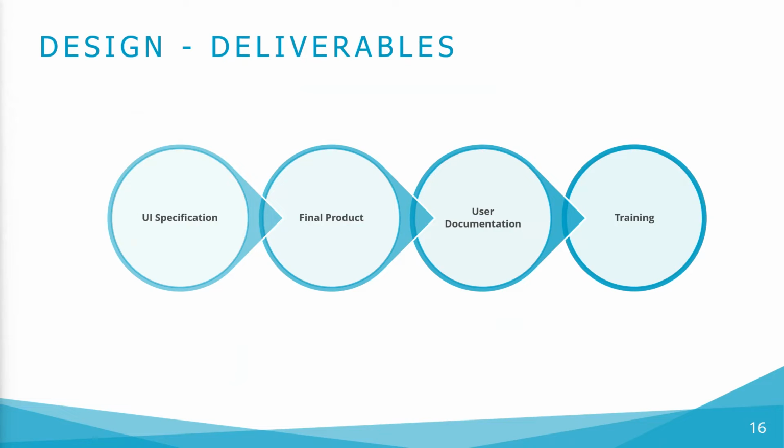After successful completion of the design step, update the following in the HFE report: description of intended device users, uses, use environments and training; description of device user interface; analysis of hazards and risks associated with device use.